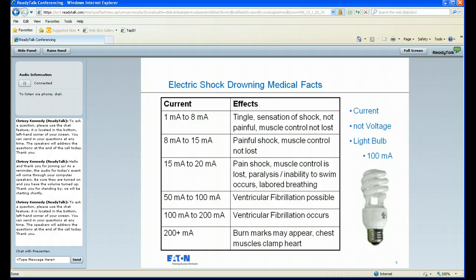That's when you have complete loss of control of being able to swim and get away from the dangers that are in the water. As you get to the higher amperage leakages, that's when you get into pretty much automatic loss of control, automatic death. To give you an idea, the current, the amperage that is leaked into the water is the big issue. It's not a voltage issue, it's the amount of current that's in the water.